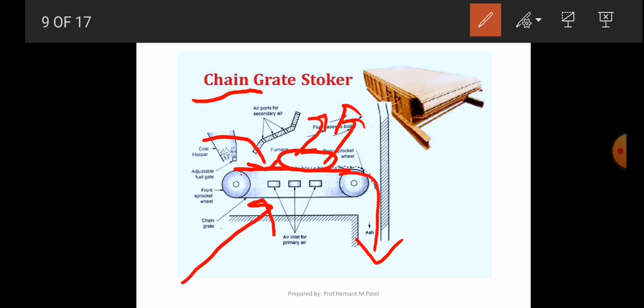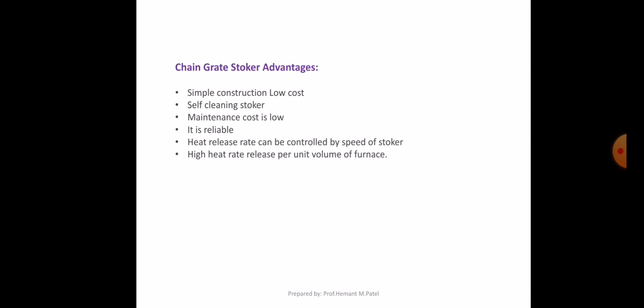Okay, what are the advantages of chain grate stoker? First of all, simple construction and low cost. It is a self-cleaning stoker, because the chain is continuously rotating, so all dust particles as well as clinker go in the downward direction. Maintenance cost is low. It is reliable. Heat release rate can be controlled by the speed of the stoker. And the last one, high heat release rate per unit volume of furnace. So these are the advantages of chain grate stoker.